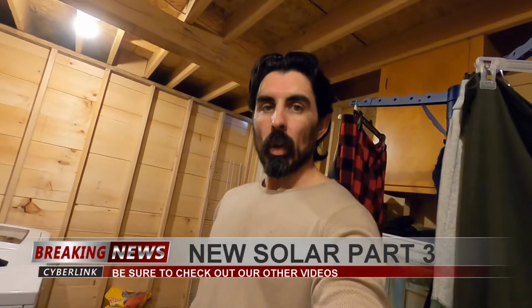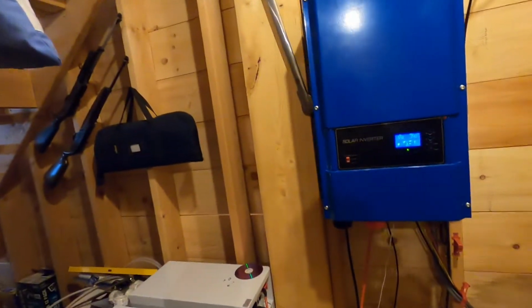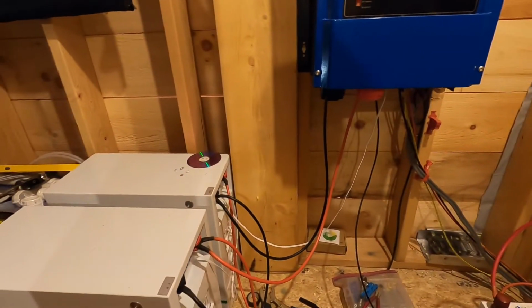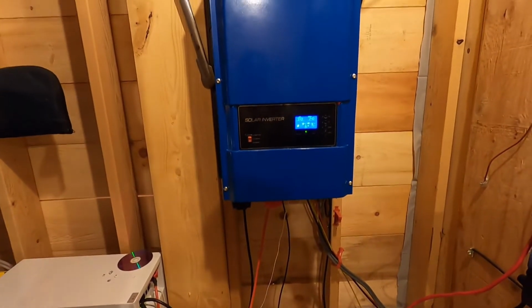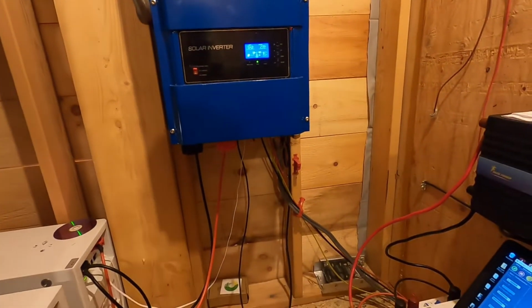All right, now, so we got all this connected up, and we got the 24-volt system removed, 48-volt system installed, hooked it all up. I was working on getting the BMS from the batteries to communicate with the charge controller, and I had it set on a manual user mode with some of the default settings, and all of a sudden, pop, it blew, which I mentioned in one of our other videos. But I'm going to go ahead and get a little more in detail about what happened and exactly what had to be done to get it addressed and taken care of.